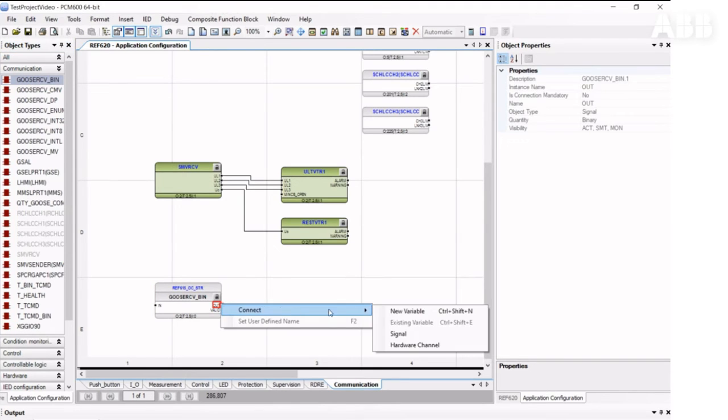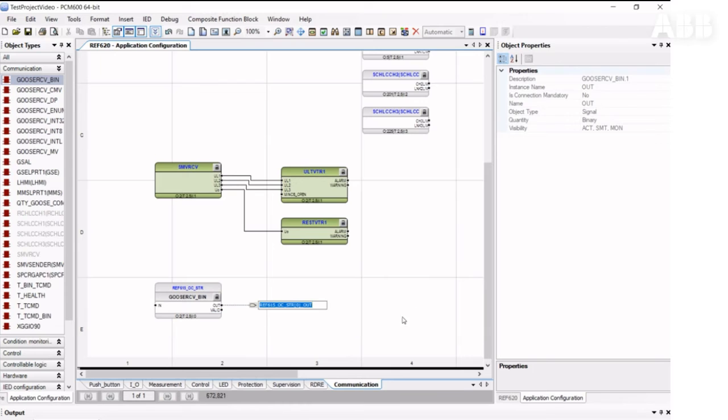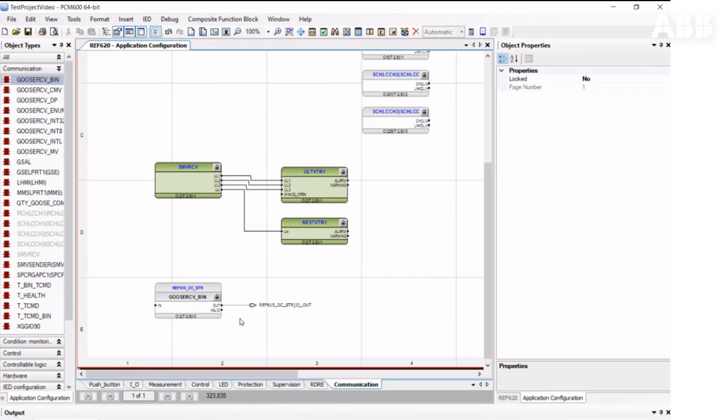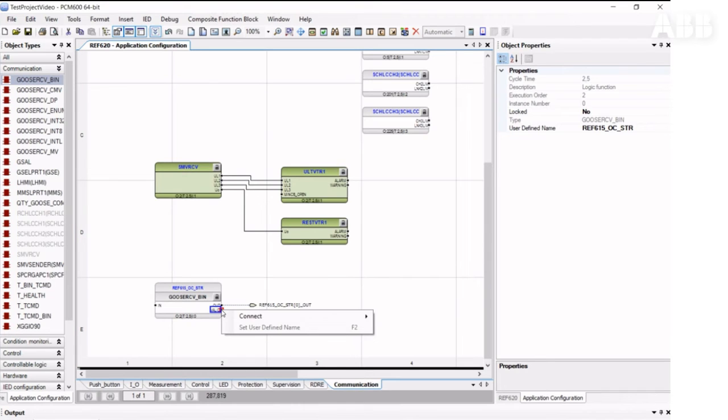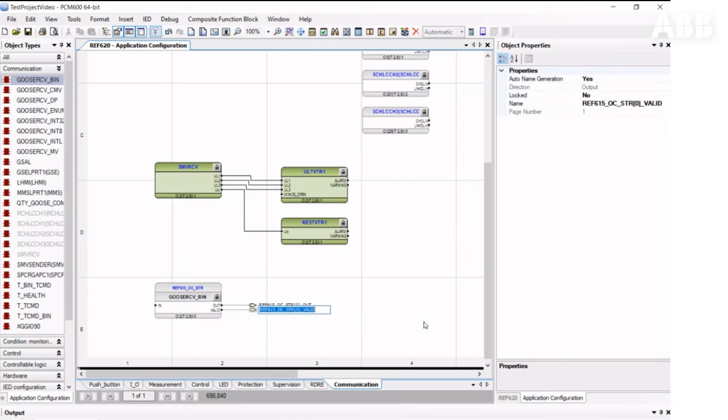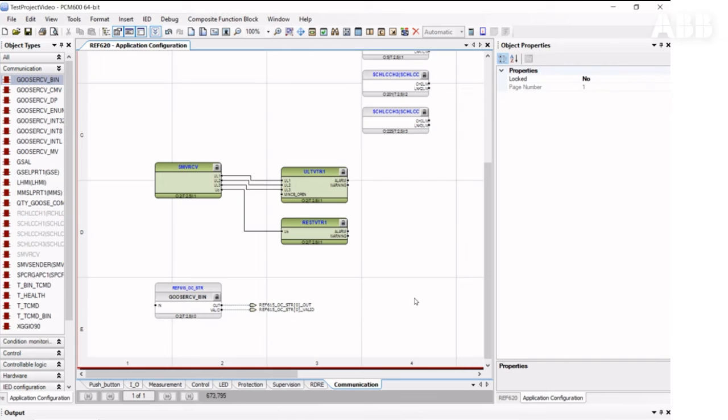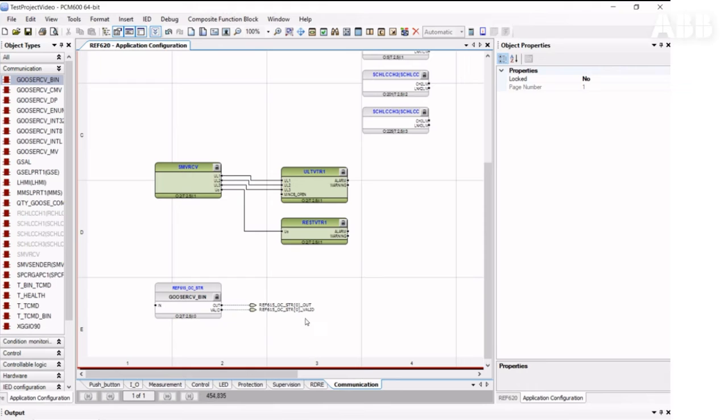Then we create a new variable from the valid output, which represents the quality of the signal. So if the quality is not good, or communication is not good between the relays, the valid signal would be false, or zero. If everything is okay, the valid signal is true, or one.